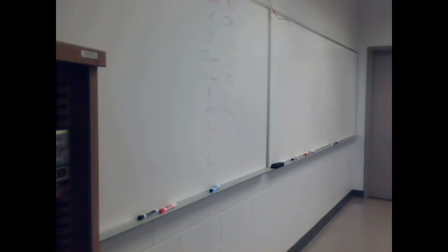Y'all may be misconstruing what this means. Y'all, hang on. So, the line was physically 50 degrees. But going inside, when you look inside that evaporator, because we maintain, in this case, 50 pounds of pressure, any liquid refrigerant that came into that evaporator changed from a 26 degree liquid to a 26 degree vapor, and then it superheated up to 50 degrees.